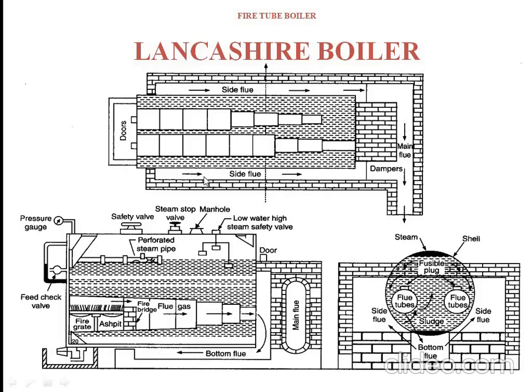From the side flue, you come to the front top view. Starting from the grate to one end is the first pass. Again from the bottom flue they come to the far front — that is the second pass. From the side flue the flue gases move to the right side. Total three passes: the main flue from grate to one end, then the bottom flue as the second pass, and the side flue as the third pass. At the end of the side channel there are two dampers, whose main purpose is to regulate the air flow.